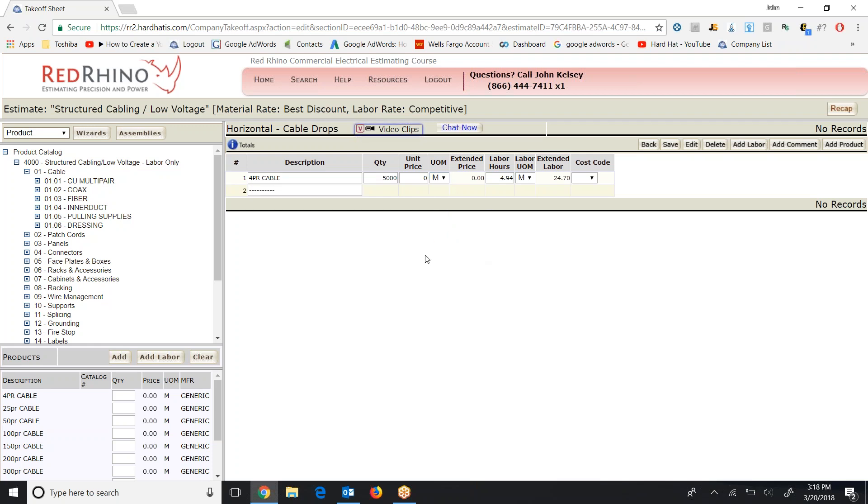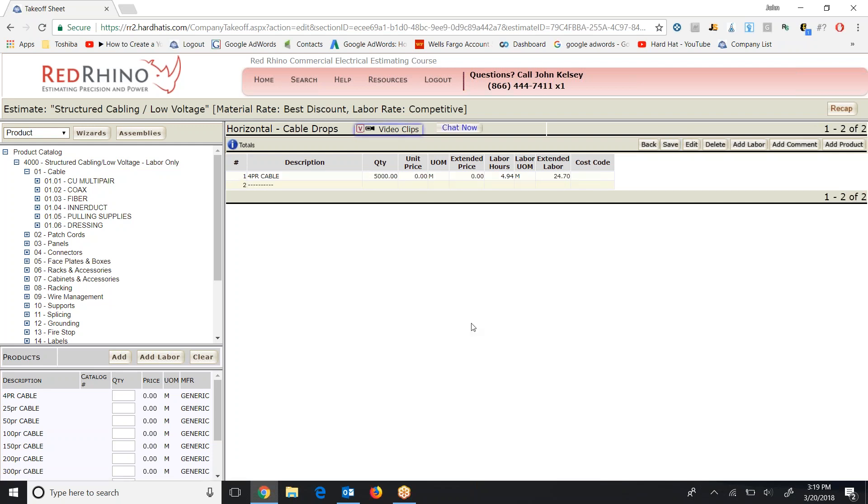So cable products you'll find are populated in here per thousand feet. So let me start over from left to right. It shows a description of the product, the quantity that was input, the price, which in low voltage items will always be zero, and unit of measure. Over at the right now, the program has a labor catalog where when you put something into an estimate, it pulls the labor from the labor catalog. This is set up for 4.94 hours to install a thousand feet of cable, the Roman numeral M. Now, when I save this over here, it does the labor extension for you. Let me just save it real quick. I click save. And when it flashes, I see that I've input the four pair cable, and it shows 24.7 hours to install all 5,000 feet.